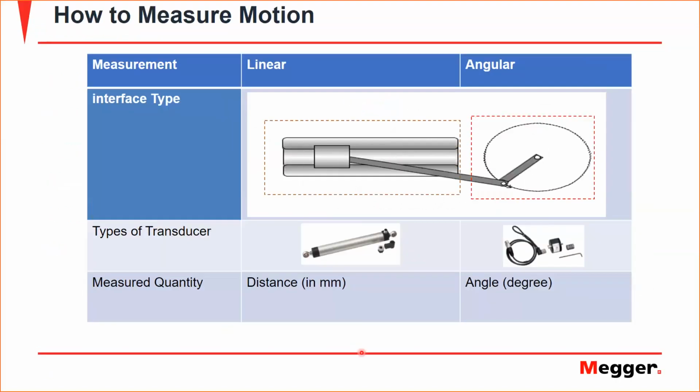Yep. All right. So in this slide, I have a quick brief idea about how motion is captured. Motion inside a circuit breaker mechanism comes in two ways. You either have a linear motion where parts go in and out, or you have an angular motion, I would say a gear that is rotating to change this linear interrupter from open to close or close to open position.